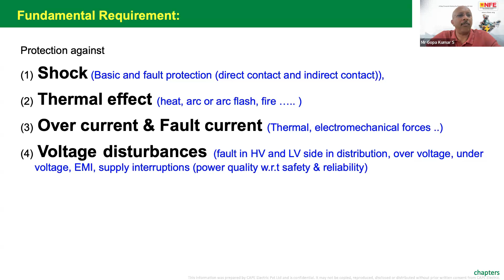Just for the information of the participants, I am showing you how complicated it is when we talk about protection from electric shock alone. The protective measures are classified into basic protection, fault protection, and additional protection in IS 732 clause 4.2. First of all, IS 732 is not a product standard. It's an installation standard. An installation standard explains how to design an electrical installation, how to select products for that particular installation, how to erect and install them, how to verify them, and how to maintain them. IS 732 is the code of practice of wiring installation. It's not a product standard.